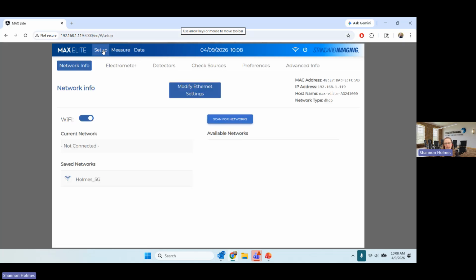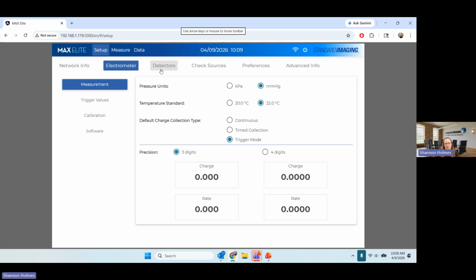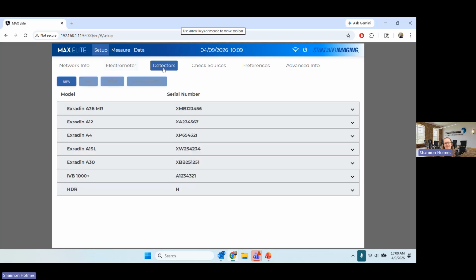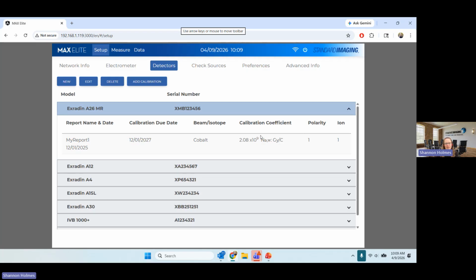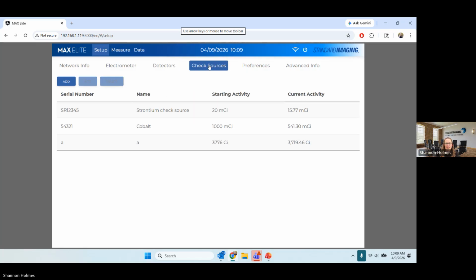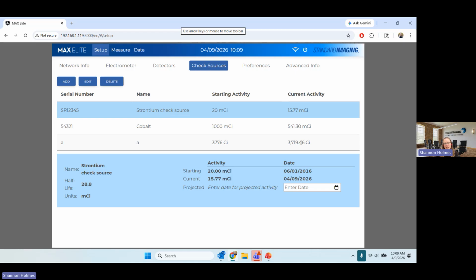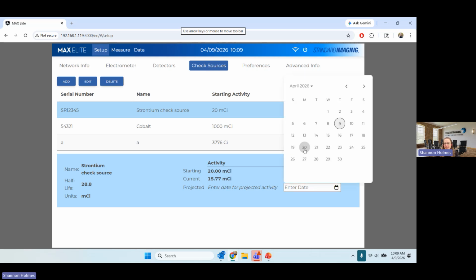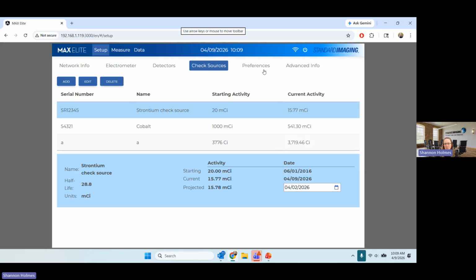But we have some setup configurations for your Wi-Fi network, or if you're hardwired for Ethernet, in order to give you your IP address, which allows you to connect to it. Settings for the electrometer are fairly self-explanatory. This is your detector library where you can have multiple detectors, have the calibration coefficients there that can be applied. We do have a check source calculation page where if you're using a check source, you can have the information about your check source in here with its starting activity and current activity for today, or if you're looking at data from a different day, you can calculate for a different day as well.